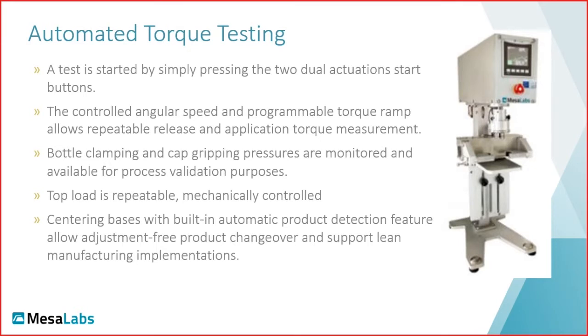Also, with the automated machine, we have pressure regulators, and these are adjustable, so the machine can apply repeatable bottle clamping pressure and cap gripping pressure. Of course, top load is also repeatable. It's applied mechanically using a spring-loaded top load chuck. And we can also offer centering bases with built-in magnets that support automatic detection and almost adjustment-free product changeover.